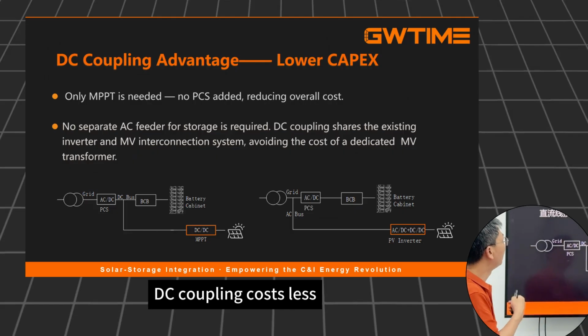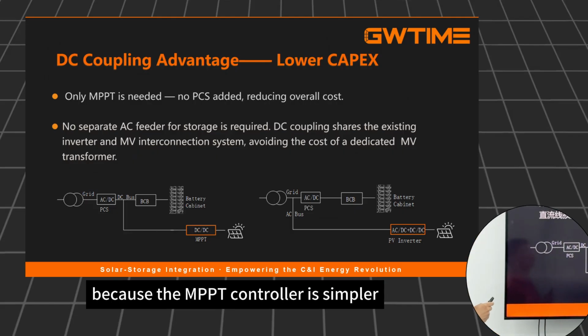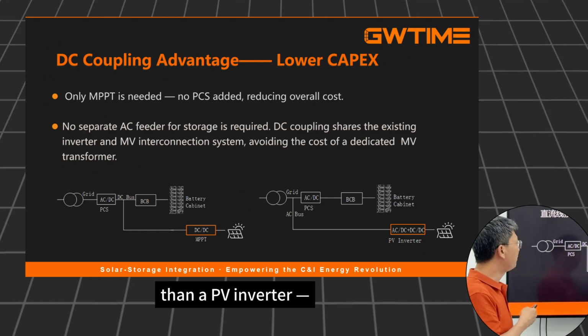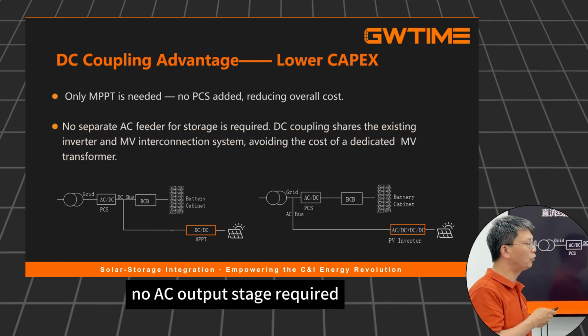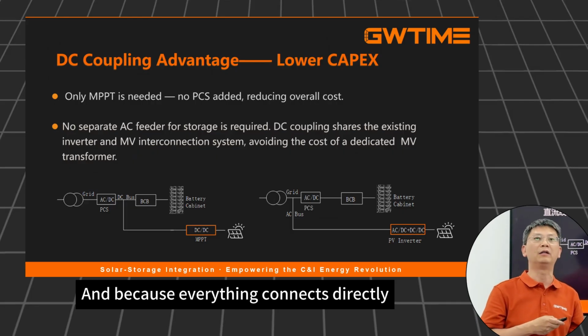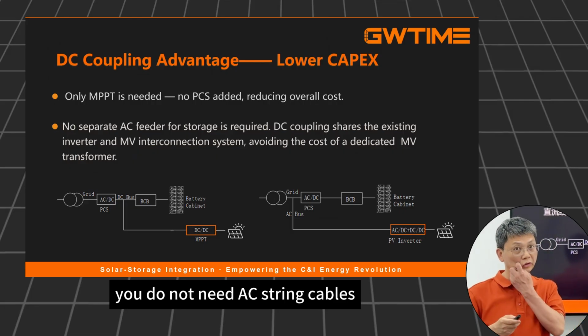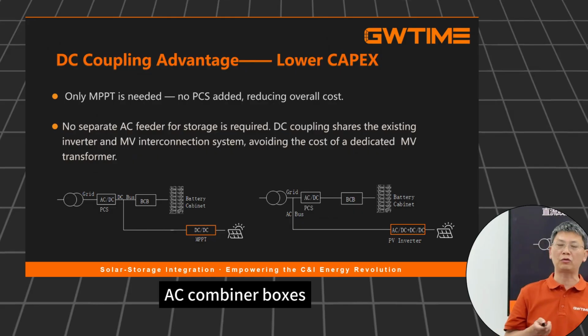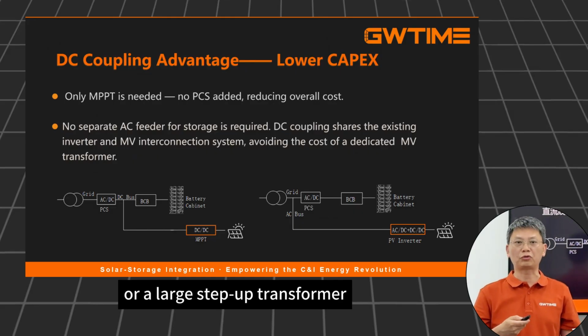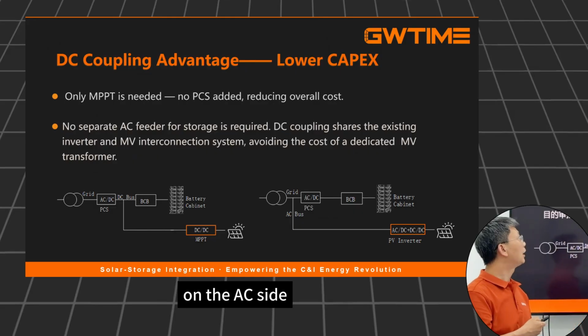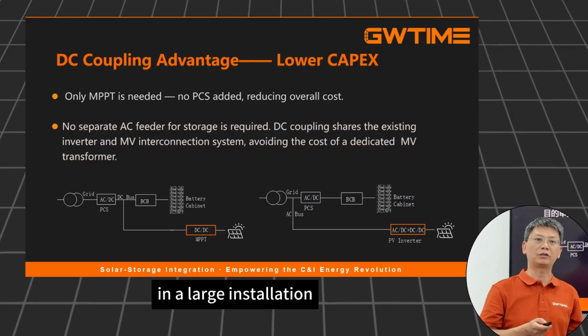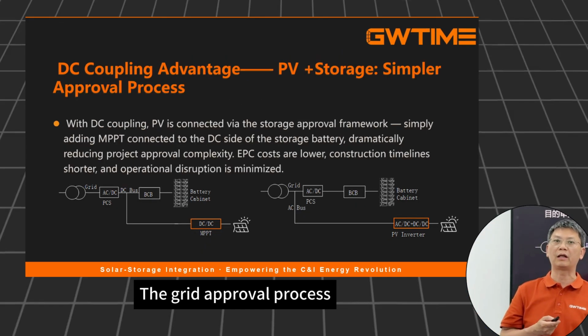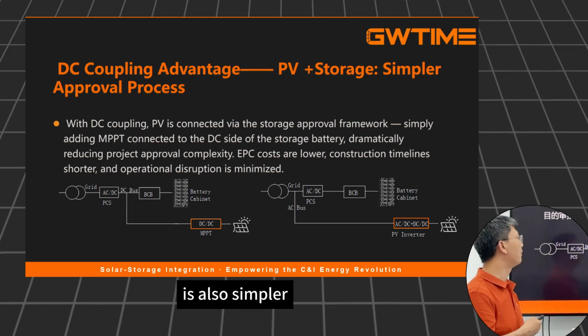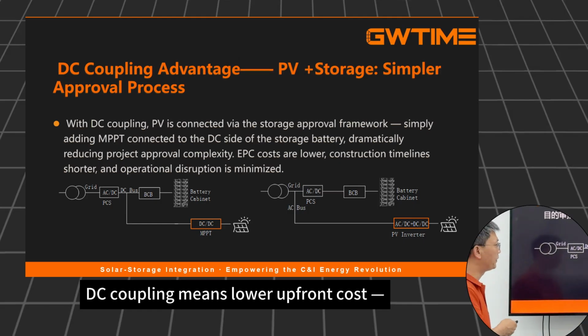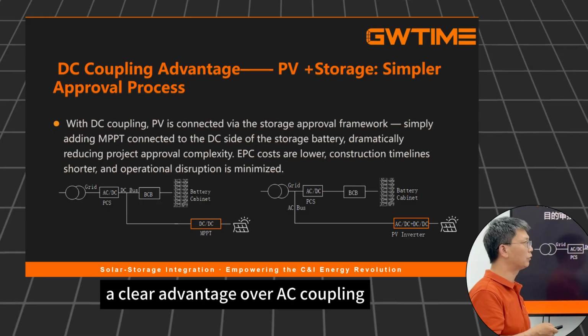DC coupling costs less because the MPPT controller is simpler than a PV inverter. No AC output stage required. And because everything connects directly to the DC bus, you do not need AC string cables, AC combiner boxes, or a large step-up transformer on the AC side. These are significant cost savings in a large installation. The grid approval process is also simpler. Overall, DC coupling means lower upfront cost, a clear advantage over AC coupling.